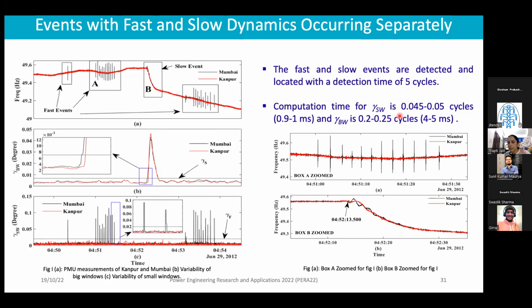The computation time for this was found to be 0.045 to 0.05 cycles, or 0.9 to 1 millisecond, and for the big window it is 4 to 5 milliseconds. Since we kept the trigger time as 5 cycles, as soon as we receive these samples, we are able to detect the event. This is the zoomed version of the plot, so you can easily see the variations for both the slow event and the fast event.